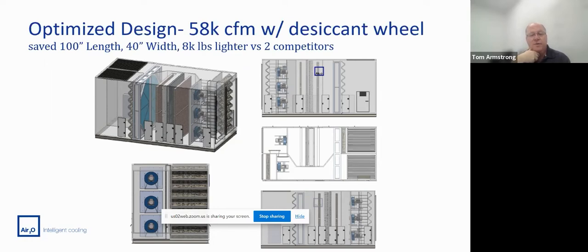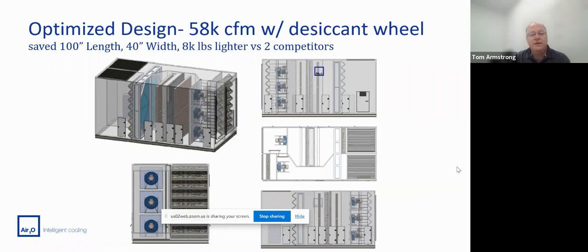The objective, of course, we want to maintain sub 500 feet per minute across the wheel on this particular air handler, but not sacrifice too much in terms of pressure drop on the other side. And the analysis showed us that we were at 0.01 inches of static was all the loss. So it was a well worthwhile trade.